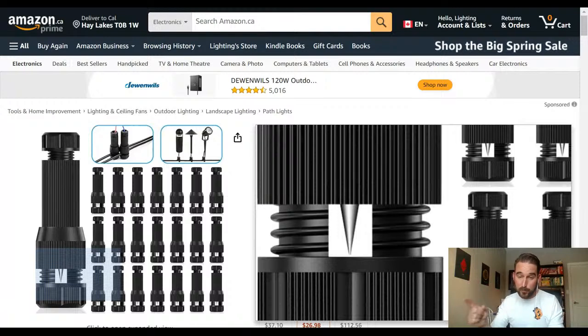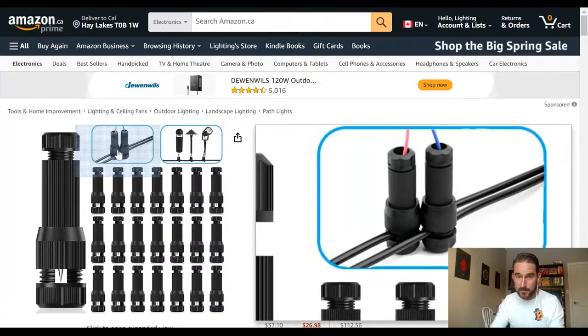The other problem with these is you can see here that you don't have any extra wires. So what people do when they put these, and this is where my last video cut out, so we're going to keep our fingers crossed. But when it's straight like this, if you have to go repair that, there's no extra wire or anything. You can't do anything. So you've got to cut back here, and you've got to cut back here, and you've got to put a whole new section in, which means now instead of just eliminating the one bad connection, you're adding two more possibilities for a flawed connection.